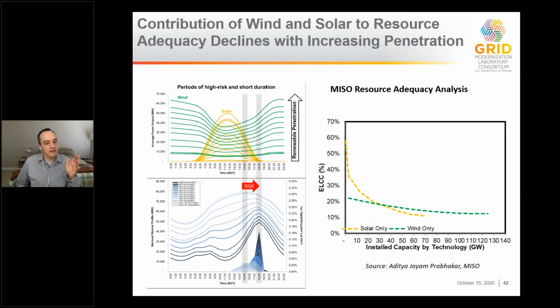So if you were to take that low penetration level, look at the production of solar during those times of high risk, and then use that to calculate what the contribution of solar would be to meeting those resource adequacy targets, which is what's shown on the right, you would find a capacity credit of solar that might be as high as about 60% of its nameplate capacity. It means if you had 100 megawatts of PV, you might count 60 megawatts of that towards helping you meet your resource adequacy targets. While wind, under those same conditions, would only get something like a 20% capacity credit.